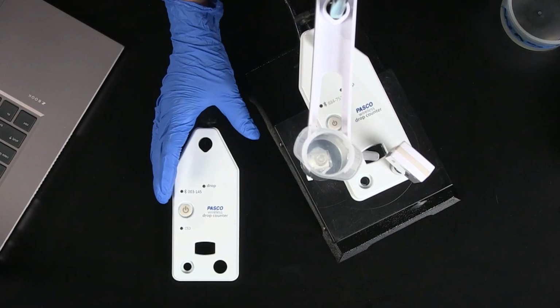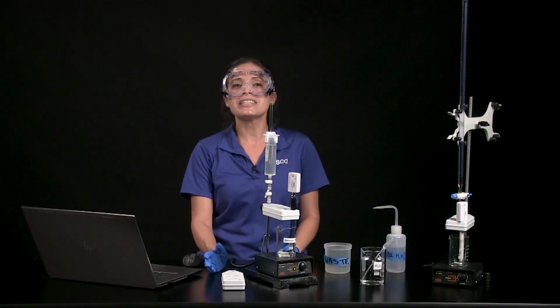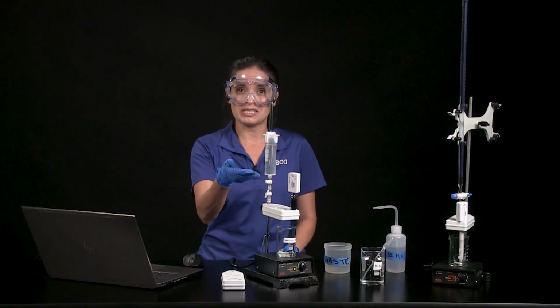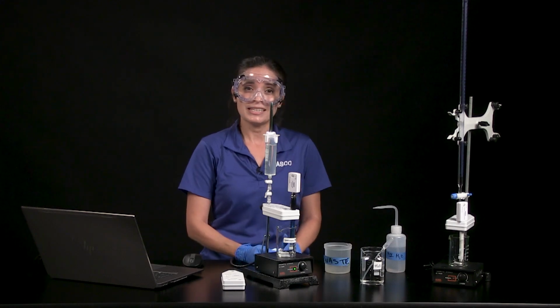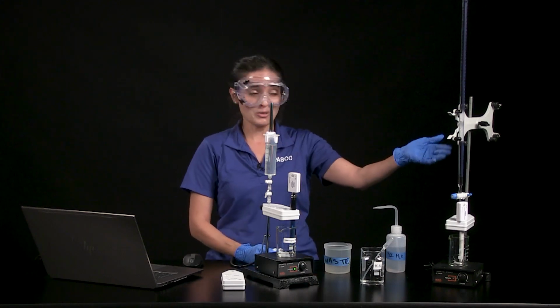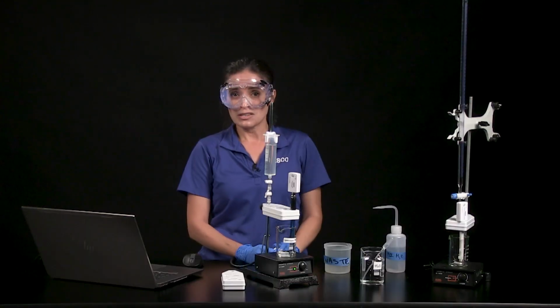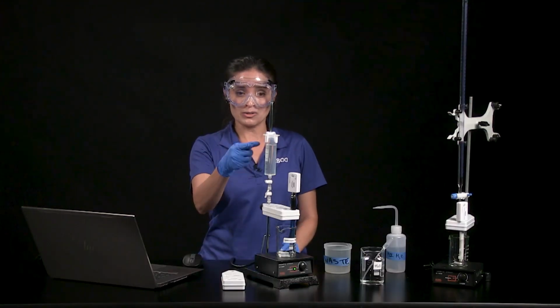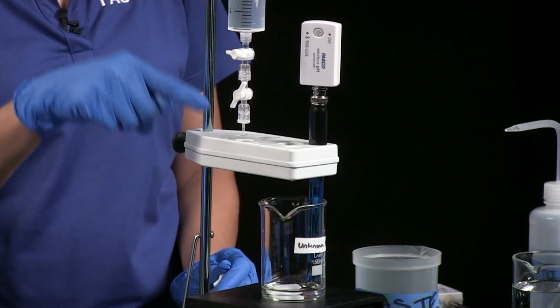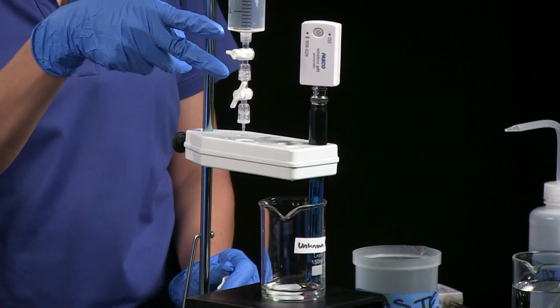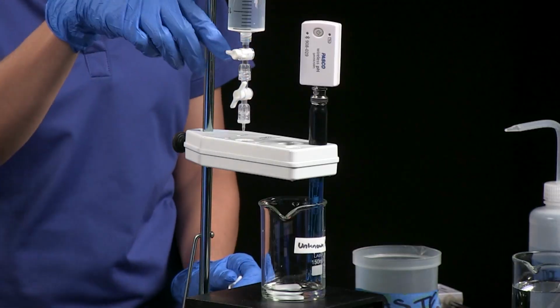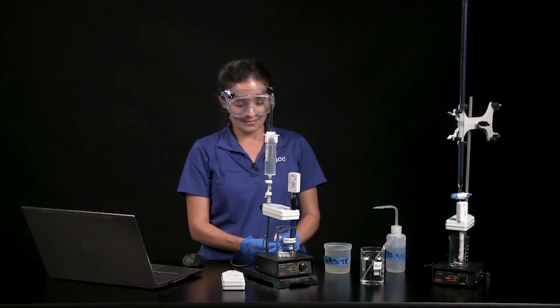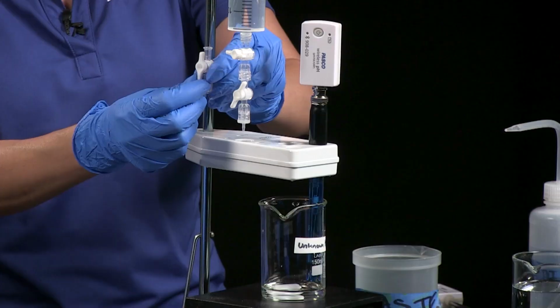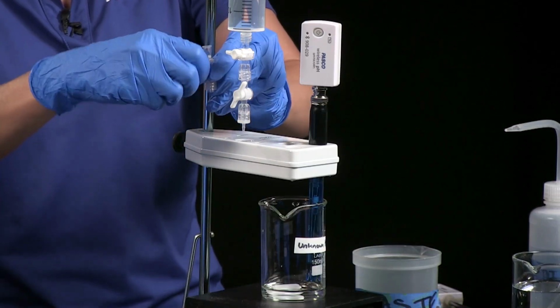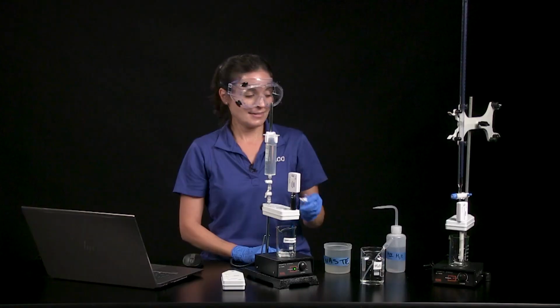PASCO's wireless drop counter comes with a charging cable and everything you need to set up a drop dispenser system that works in place of a traditional burette. But a traditional burette also works great with the drop counter. The drop dispenser system includes a solution reservoir, clamp, 2 stopcock valves, and a drop tip. Both stopcock valves are hand-tight, and valve controls are both accessible. The valves are open when the controls are vertical and closed when horizontal.